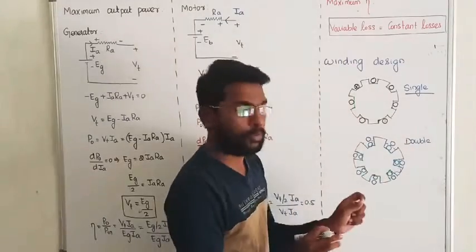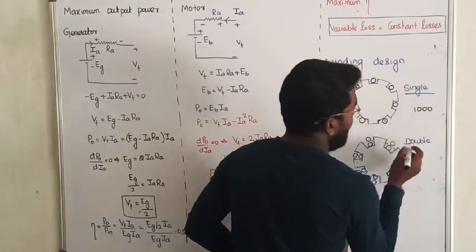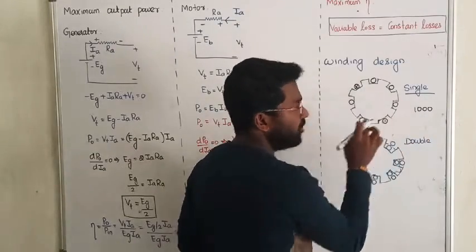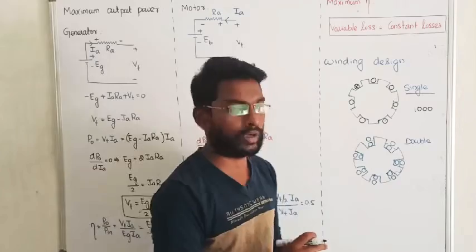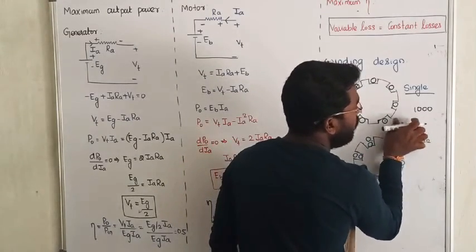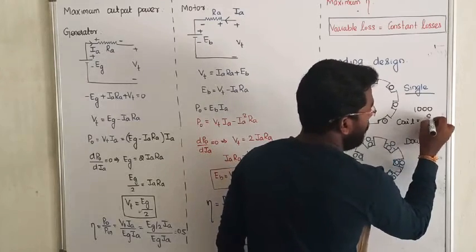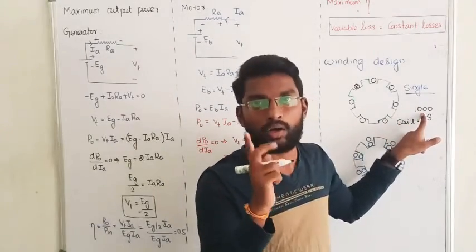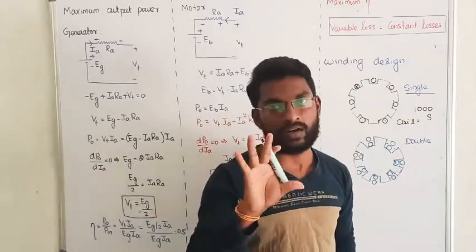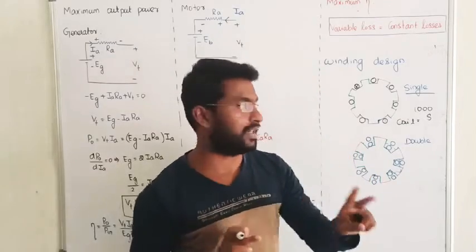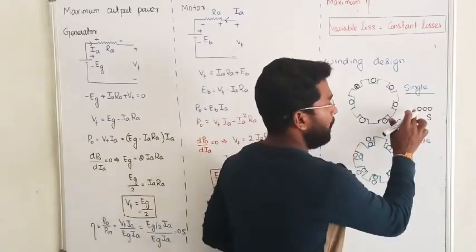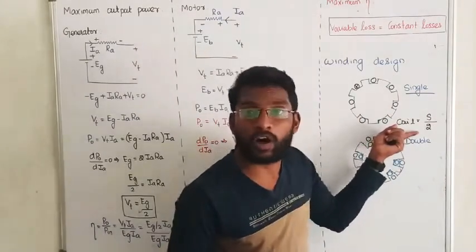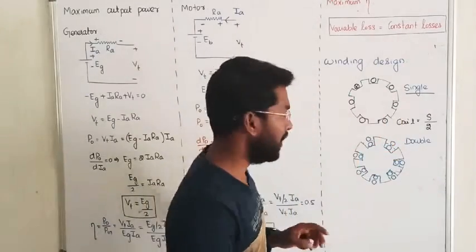In case of single layer winding, suppose you have 1000 conductors — one conductor per slot, so 1000 slots. Total number of conductors equals number of slots. Since one turn requires two conductors, 1000 conductors give 500 turns. So in single layer winding, the number of turns equals half the number of conductors, or equivalently half the number of slots. Number of coils equals number of turns equals total number of slots divided by 2.